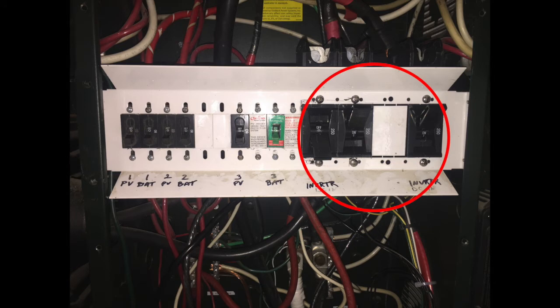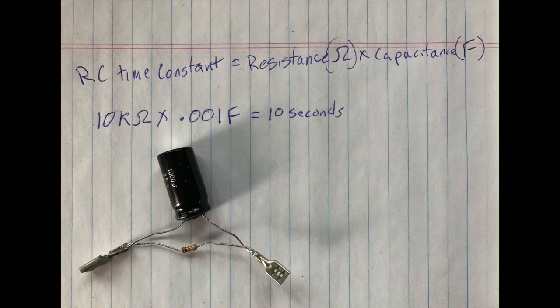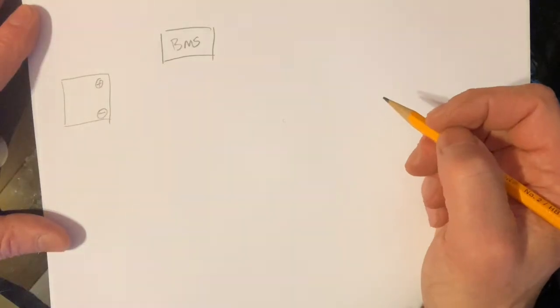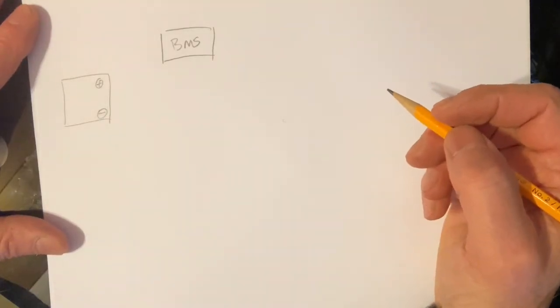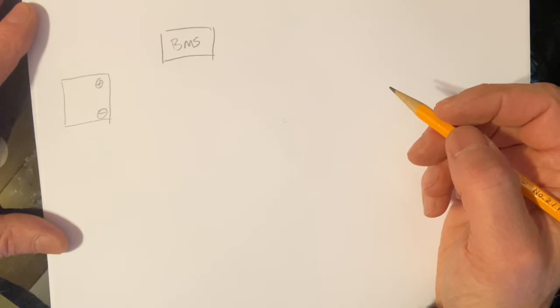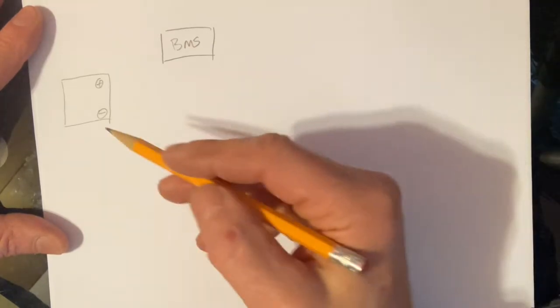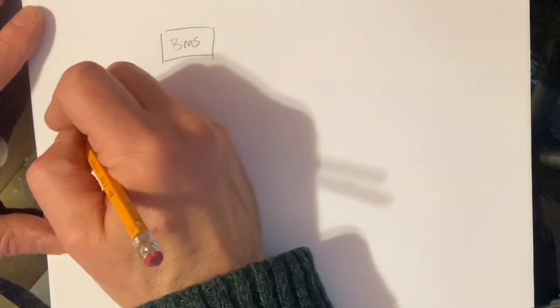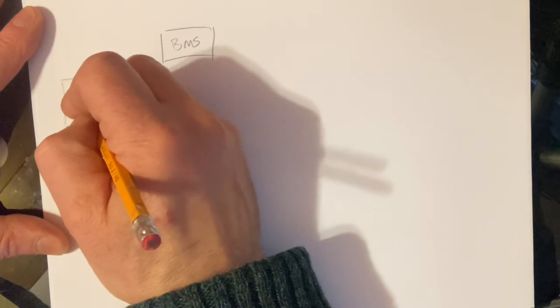The shunt trip breakers only need a brief voltage pulse to activate and open. The coils will burn up if you leave the power connected to them for more than about 15 seconds. This required installing a simple resistor capacitor network as a timer for each of the shunt coils. I know there's going to be some questions on how the control circuit works and how it gets wired together. So I'm going to start with a simple schematic with our basic building blocks.